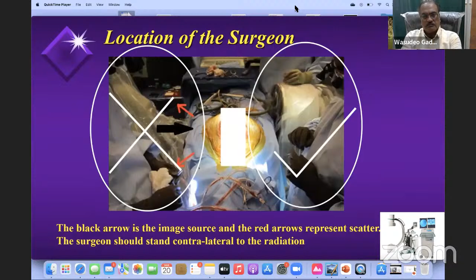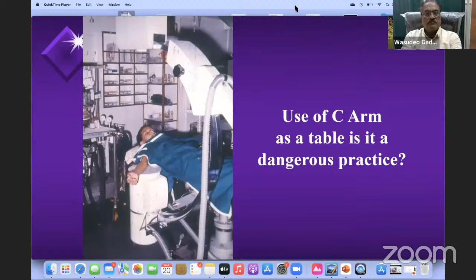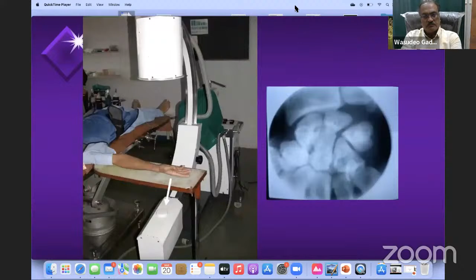So we said that the X-ray generating unit should be under the table, but the majority of us use the IITV itself as a table to operate, especially on the hand and elbow. Is it a dangerous practice? So this article, which appeared in JBJS in 2001, said that if you are using the C arm itself as a table, especially for smaller parts like the moving parts of the hand and wrist, then it reduces the radiation.